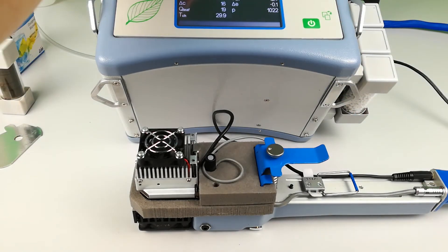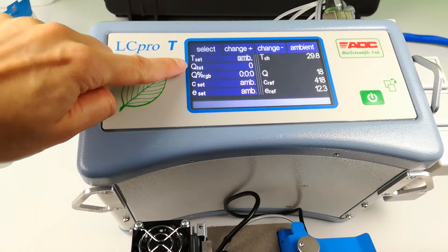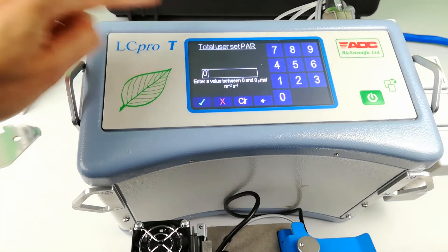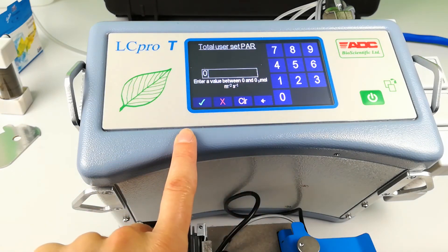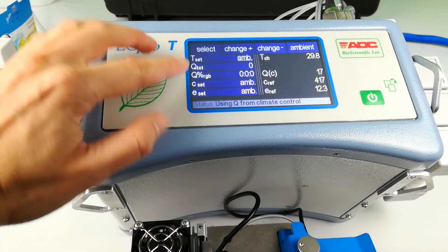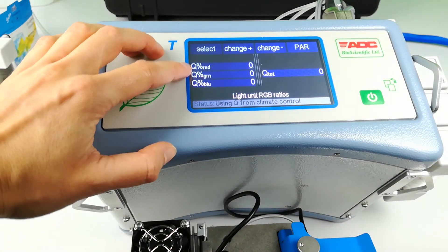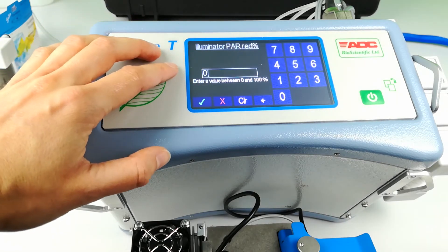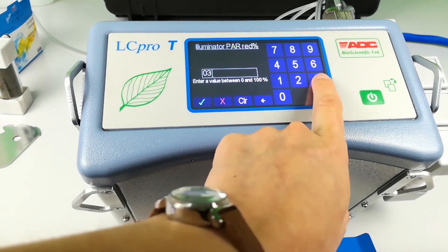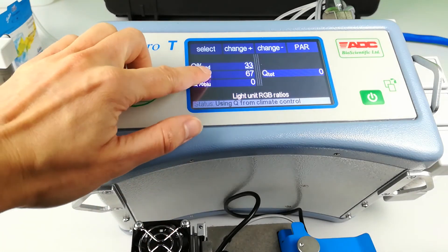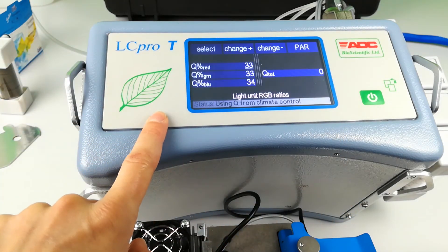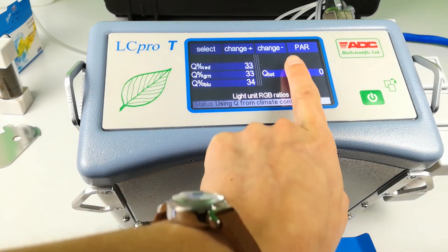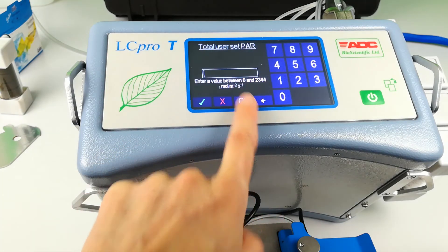From the climate menu you can see Q-Total to set the total PAR. The range says zero until, with the RGB light unit, you have set the relative quantities of R to G to B. First set the red LEDs, entering a value using the keypad. Here we will set R, G and B to equal quantities. The software rounds to the nearest whole number.